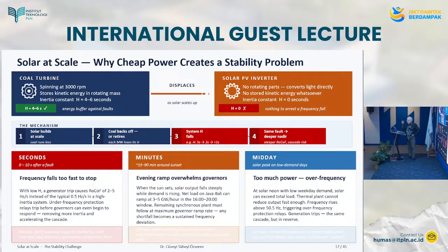Okay, so that's one problem. Another one requires 15 to 90 minutes around sunset. When the sun sets, solar output falls steeply. So if you've got a lot of solar generators in the system, at the evening peak there is no solar, right? So what you have to do is increase the output of your existing coal-fired or gas-fired generators. But generators cannot go from 0 to maximum instantly. So, like cars, they have to accelerate, which is called the ramping rate of a generator.